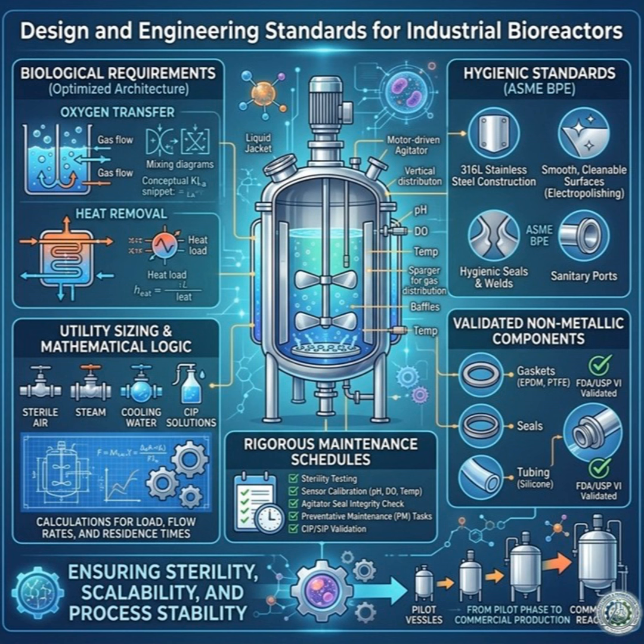This brings up a major design danger the text highlights, something called dead legs. It sounds ominous. What exactly is a dead leg in a bioreactor? A dead leg is any section of piping or a sensor port where fluid or steam doesn't actively flow through. Imagine a short, dead-end pipe branching off the side of the main tank. Okay. When you flood the main vessel with 121-degree steam, the ambient air trapped at the end of that dead-end pipe might act as an insulating cushion. The steam can't fully penetrate it. So it creates a microscopic cold spot. A cold spot that might only reach, say, 110 degrees. If a single spore survives in that dead leg, the moment you fill the tank with warm, rich nutrient media, that spore will wake up, wash into the main tank, multiply exponentially, and destroy a batch that might be worth millions of dollars. Easily. Designing out every single dead leg and ensuring perfect steam flow is an absolute obsession in biomanufacturing.